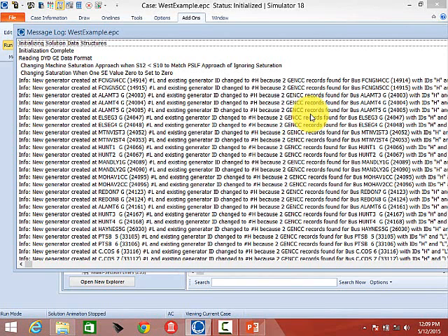What Simulator does is it knows about this. It knows that we have to split that generator up, and we split it up. It's known as a cross-compound unit, and it's represented now as two generators, and then we log that it occurred. That takes place transparently. You don't have to be concerned about it, but it's something to know about. So there's going to be two generators internally. It actually does put two generator units. You don't want to save it and compare it to your original power flow because it has changed the power flow. Yes, there are now two generators at that bus. It split it.